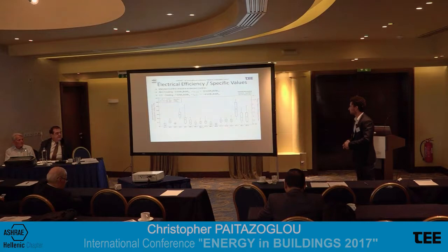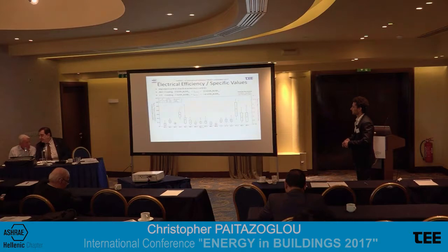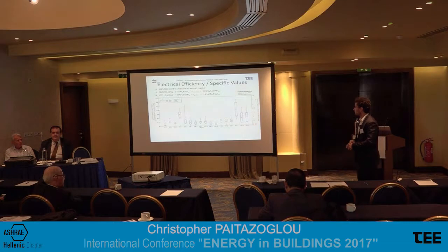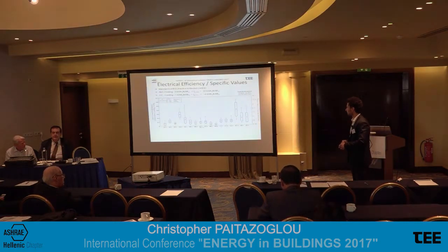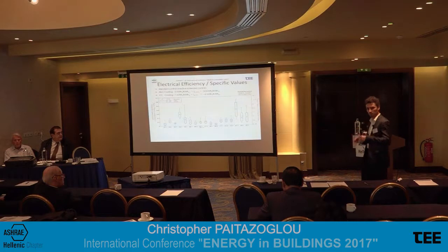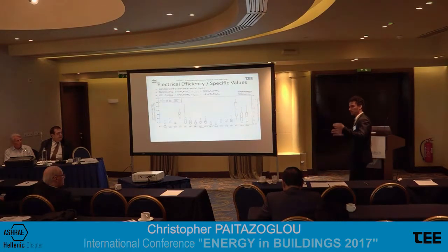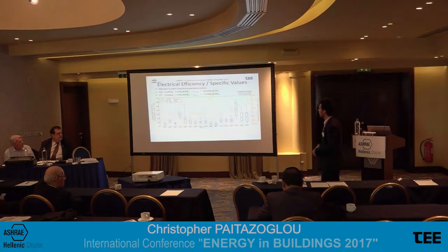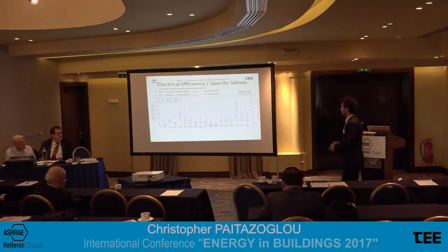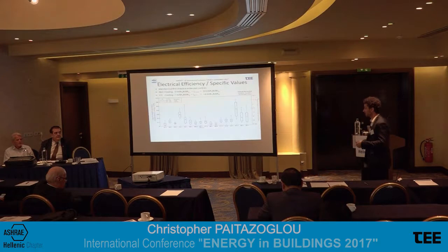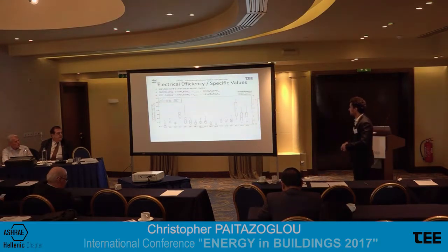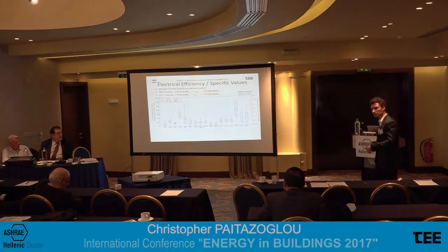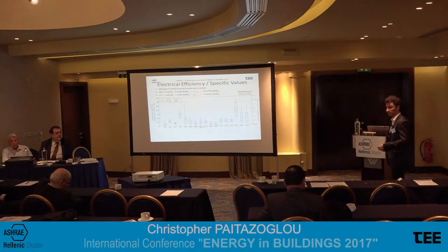Here again, the sites over the electrical COP, or the reciprocal of that, that is the specific electrical consumption. We see in this diagram for all sites three main things about one plot here. That is the mean value, that is the cross. The blue box is representing 20 to 80% of the spread that we have in the values, and the other line is representing 5 to 95% of the daily values that have been calculated. So we see here that in total, the systems are operating in between 5 to 32 kilowatt hours of cooling per electricity.